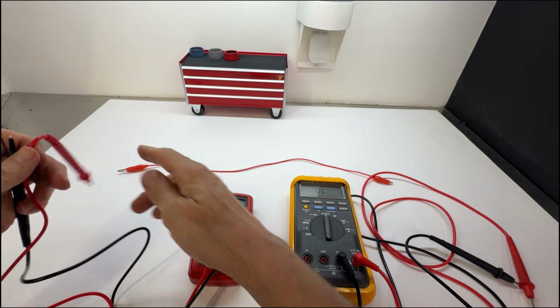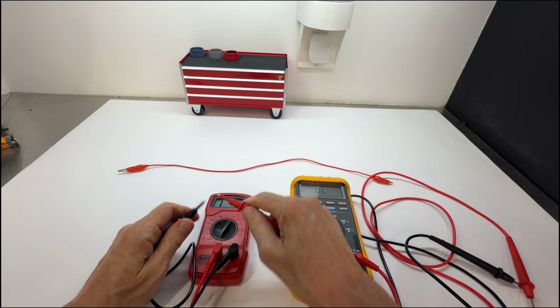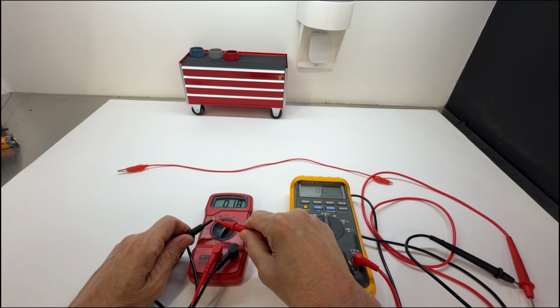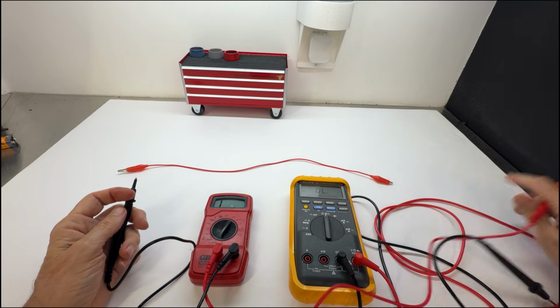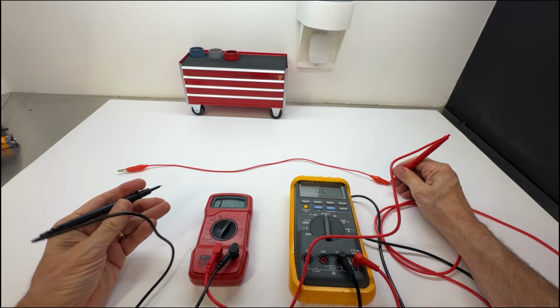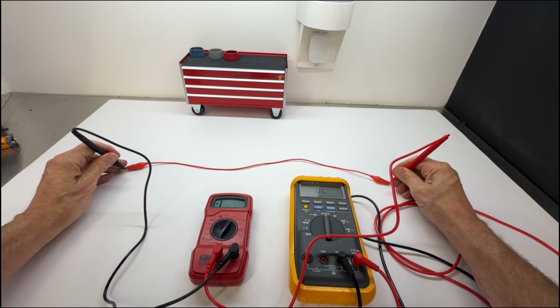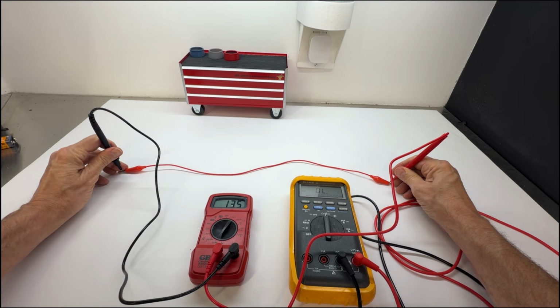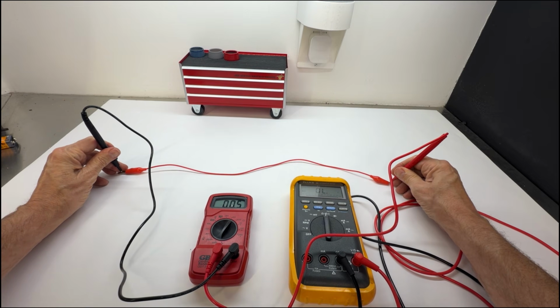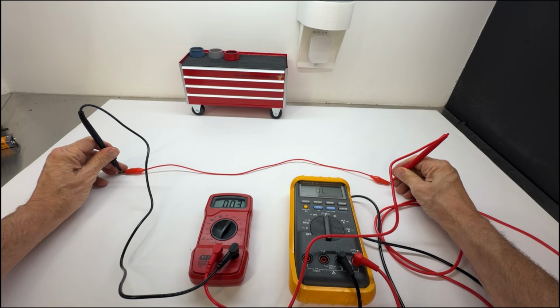It doesn't have a beep or anything like that because it's not fancy. But when you touch the two probes together, the reading should go to zero or pretty close to zero, just like that. Then you can check your circuit the same way, putting one probe on one side and one on the other. Again there's no nice beep, but you can see it has about 0.4 ohms of resistance, and that is good continuity, so that alligator clip is good.